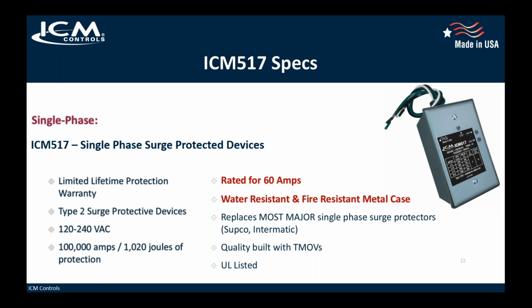A whole house surge suppressor is a Type 1 device. That has to be installed by a certified electrician. But these types of devices can be installed by your contractors, HVAC technicians, because they're on the load side of the line. These represent protection for 120 and 240 volt applications. As I mentioned, the surge protection rating, the surge current, is 100,000 amps.